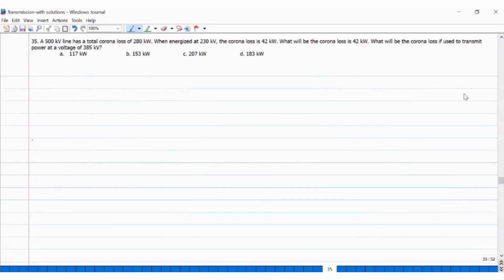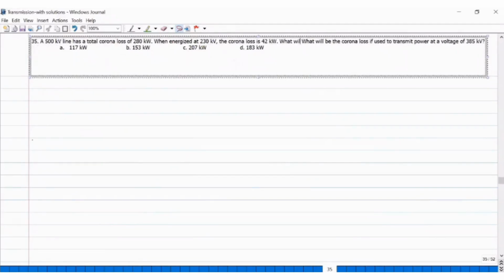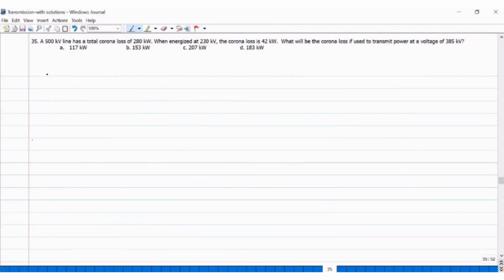35. A 500 kV line has a total corona loss of 280 kilowatts. When energized at 230 kV, the corona loss is 42 kilowatts. So what will be the corona loss if used to transmit power at a voltage of 385 kilovolts? So sa mga hindi pa naka-encounter ng formula, the corona loss for the first case is K times the voltage per phase of the source, so source voltage minus the critical disruptive voltage, then raised to 2.